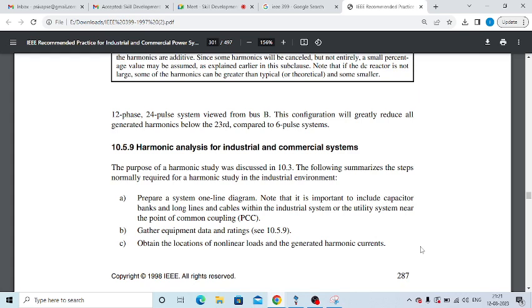So those loads are called non-linear loads. Those non-linear loads are mostly made up of power electronic based converters like rectifiers, chargers, VFDs, solar inverters or wind turbine generators, cycloconverters. Other non-linear loads include the electric arc furnace. These are some of the non-linear loads we normally use in the power system. This equipment will introduce non-linear characteristics into the system. These non-linear characteristics are called harmonics. These harmonics will introduce many more frequencies into the fundamental frequency of 50 hertz or 60 hertz. Those frequencies are called non-linear frequencies.